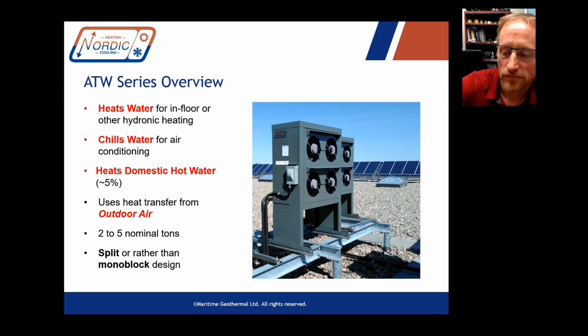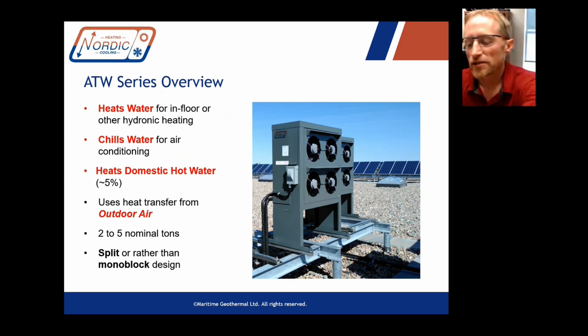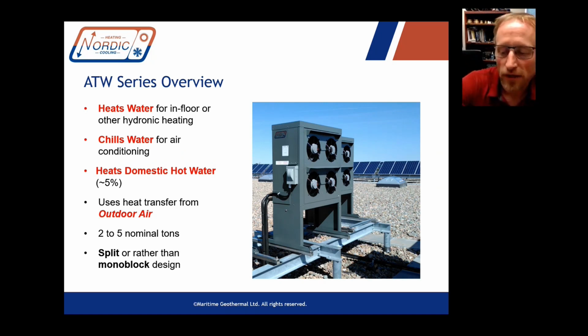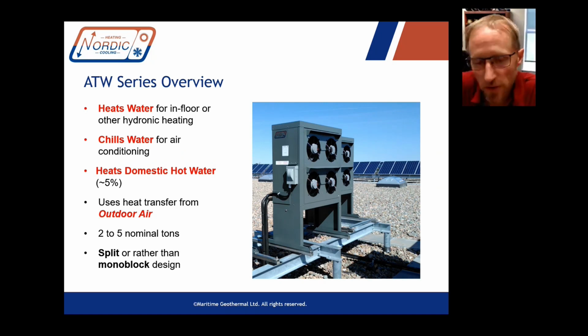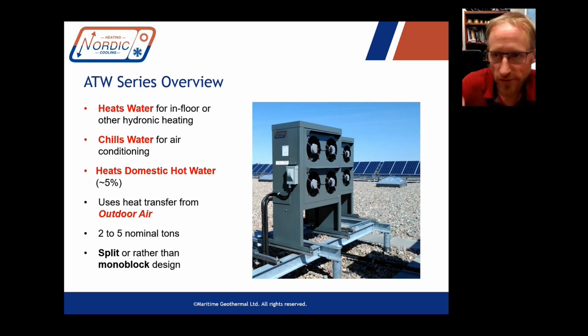So you've got, say, a 5-ton unit. Now you want to have hot water. You have a call for hot water. You need to heat the hot water tank. So yeah, it's not call based for sure. It's not an on-demand domestic water heating device. What it does is, while the compressor is running for space heating or cooling, the hot gas from the compressor is always going through a double wall heat exchanger that's connected to the domestic water preheat tank. And there's a built-in circulator that circulates water through there. So it can heat domestic water.